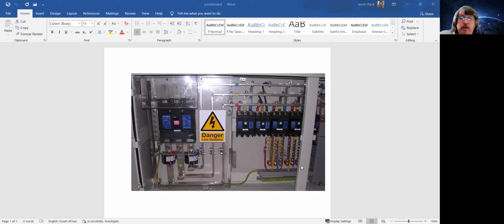So firstly, if we have a look, it looks fairly neat. It's coming in on the top here, going out on the bottom. So it's what I call normal feed, not reverse fed. It's connected to bus bars, connected and switched around and supplied to the top. On some of them, they do have wires connected, and some have bus bars connecting. Possibly these are higher ratings than those. The bus bars themselves are plated, so they look pretty attractive from that avenue.